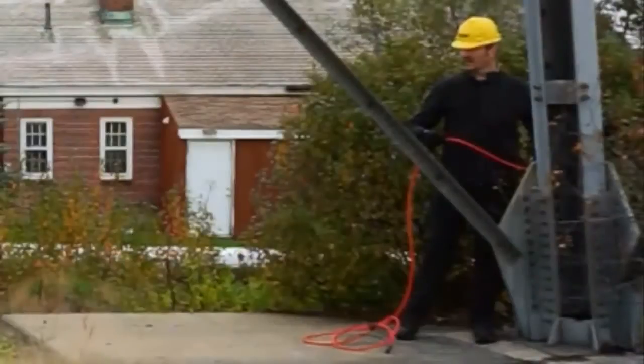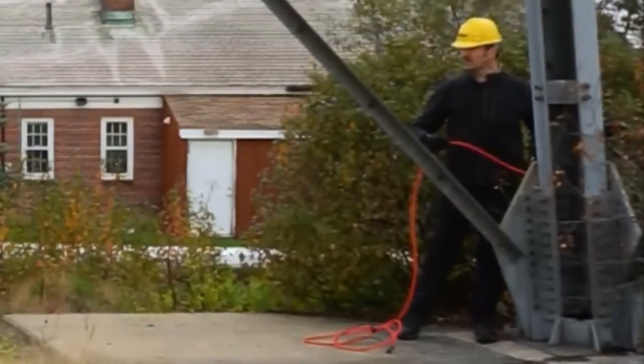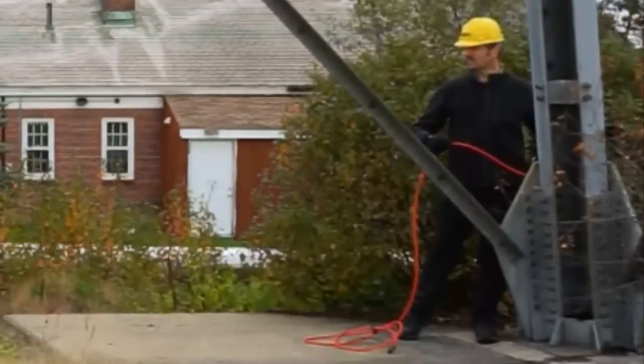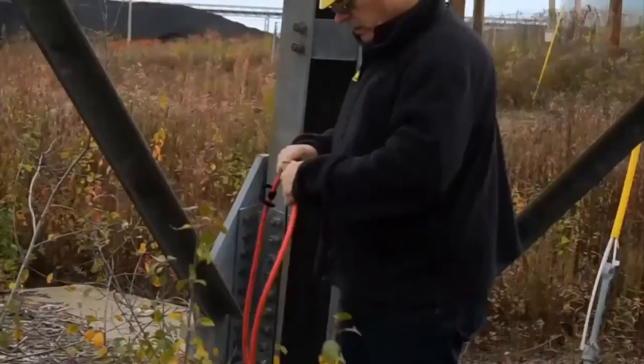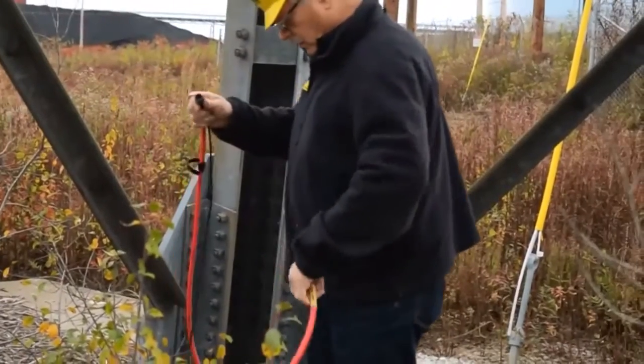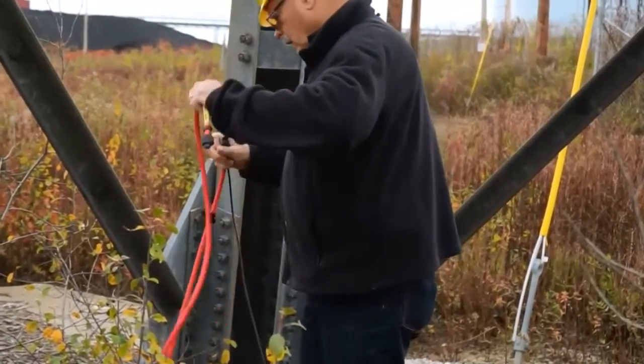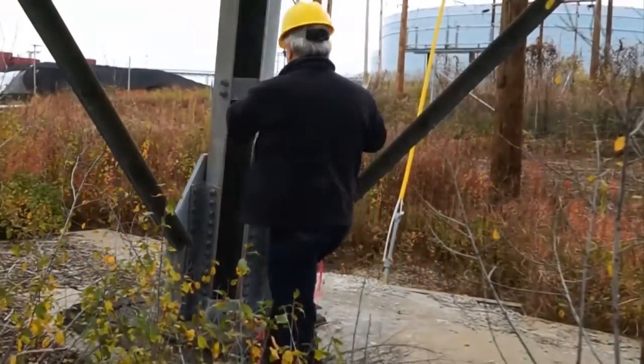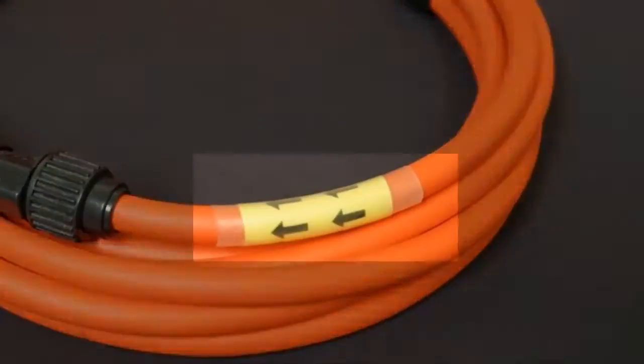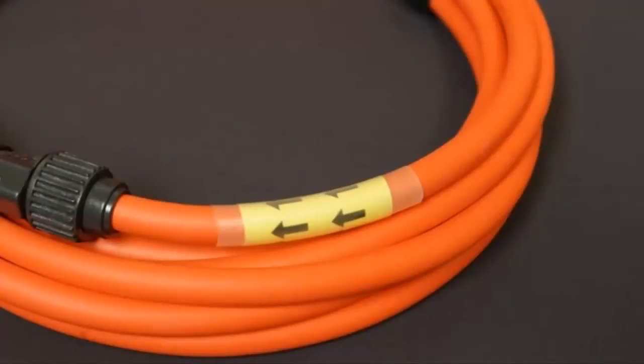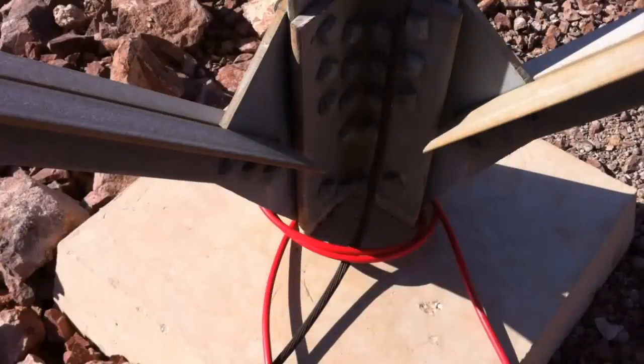Next, install the GroundFlex sensors around each leg of the tower. A sensor can be looped around the leg up to 4 times. The more loops used, the more precise the measurement. All sensors used in the test must be looped the same number of times. Note that each sensor is labeled with arrows. For all sensors, these arrows must be pointing in the same rotational direction on each tower leg. In this test, we will loop each sensor twice, counterclockwise.